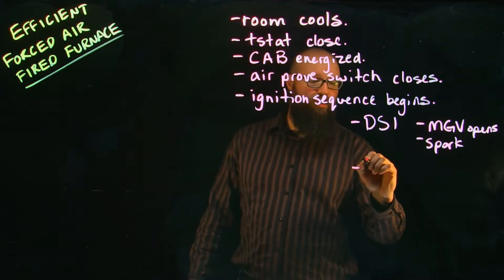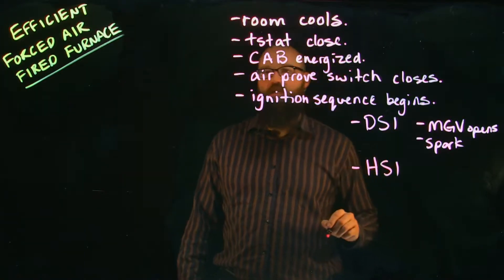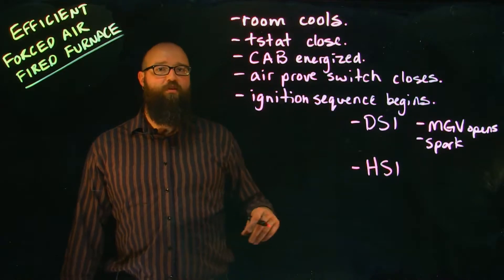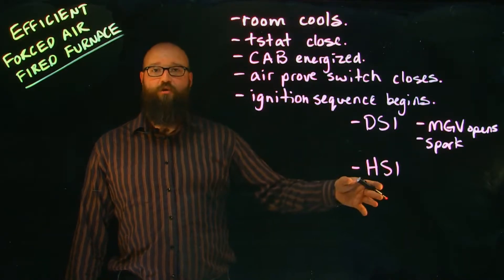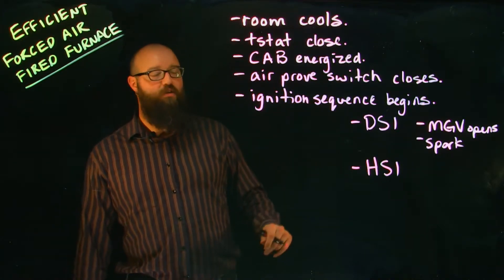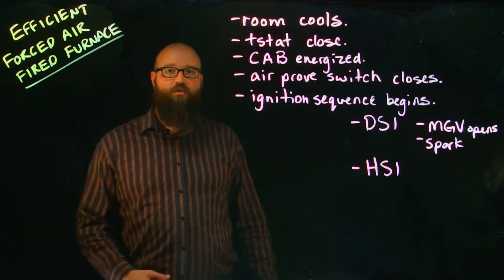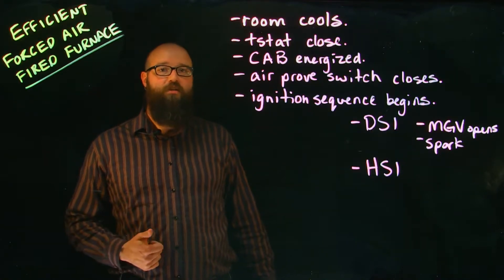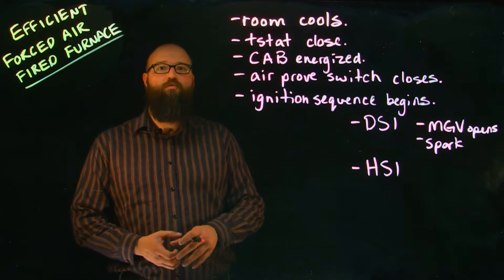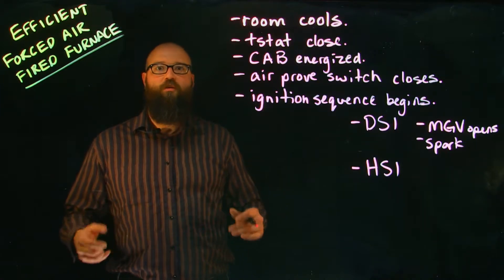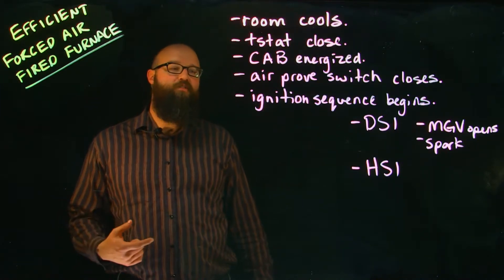If we're looking at an HSI or a hot surface ignition, depending on whether we're looking at intermittent or just a hot surface ignition, the first thing that is actually energized is going to be that hot surface element, which is going to be allowed to start to get really warm. It starts to glow and then after a certain amount of time, then the gas is released.